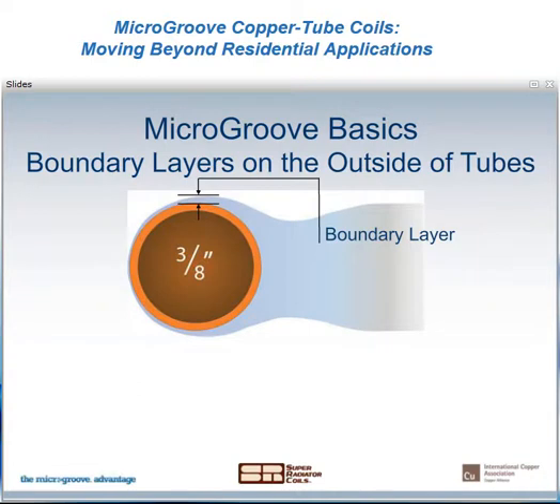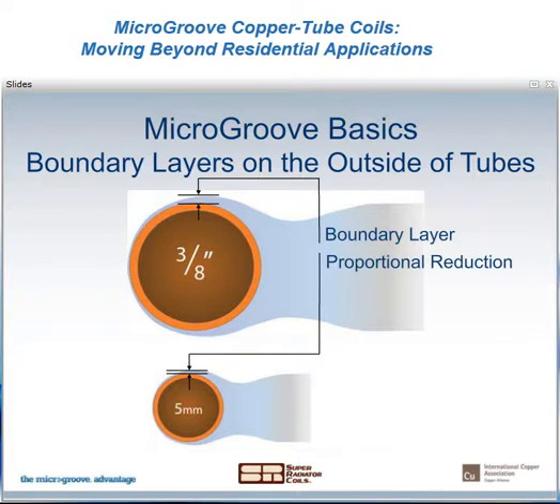Now air, being a fluid, also forms a boundary layer on the outside of the tube, just like refrigerant forms one on the inside. But if we look at the boundary layer that forms outside of a 3/8 inch or a 9.5 millimeter tube, and we compare that to the boundary layer outside of a 5 millimeter tube, you'll see a considerable reduction in the size of the boundary layer outside of the smaller tube. And this reduction in boundary layers further improves the efficiency of the heat transfer in coils with MicroGroove tubes.